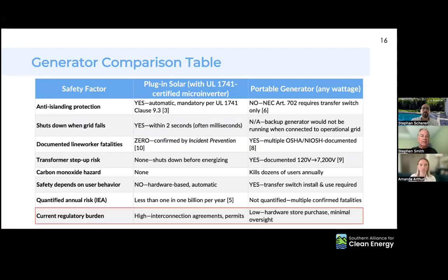When we were looking at the comparison between plug-in solar with a UL 1741 certified microinverter, we created this list from the white paper. Anti-islanding protection means the inverter will immediately shut down generation so it cannot access and backfeed. That is a requirement on plug-in solar, but it is not required for generators—they require a transfer switch, but that's separate from the actual technology of the generator itself. So when the grid goes down, solar shuts down in less than 2 seconds, often in milliseconds, while a backup generator could still be running and connected to the grid. When you look at the actual track record in safety, there are zero documented lineman fatalities from plug-in solar with inverters.